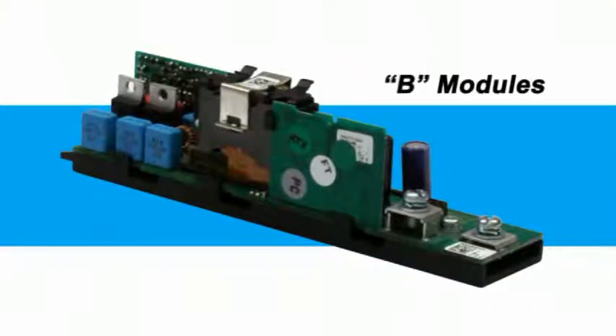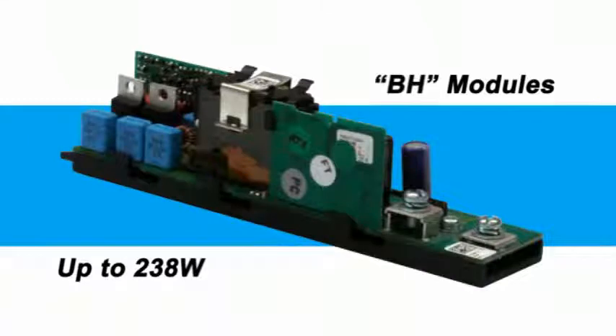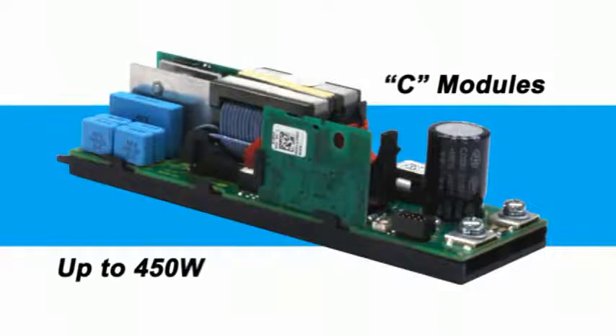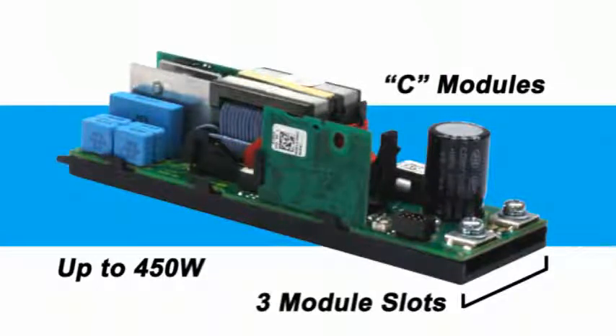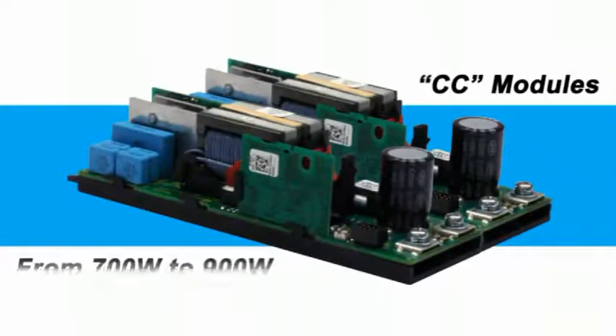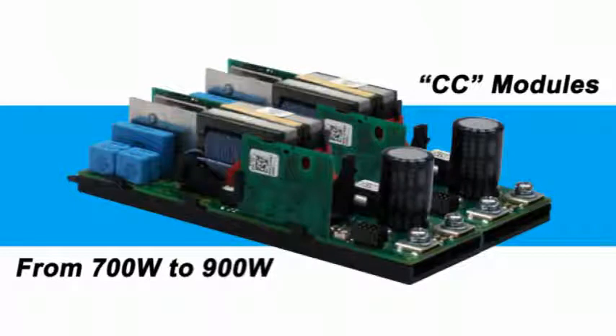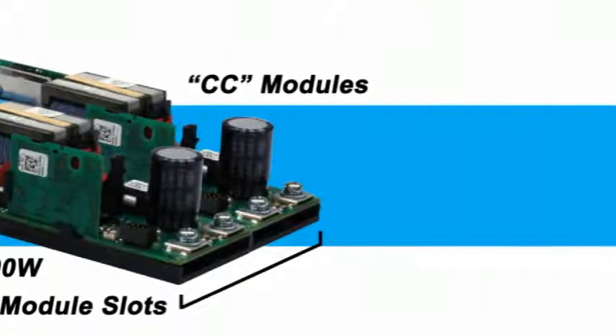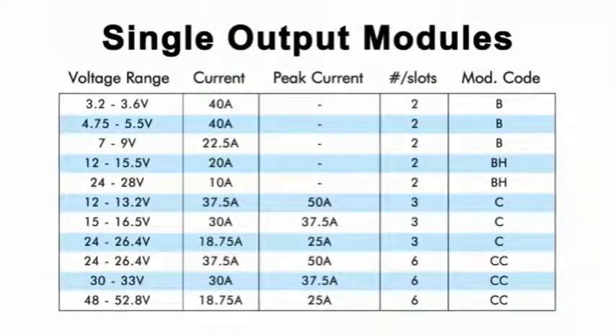These include the B modules up to 200 watts and BH modules up to 238 watts that take up 2 module slots. The C modules up to 450 watts are 3 slots wide and include a microprocessor to increase its power density, performance, and reliability. The CC modules from 700 watts up to 900 watts use 6 slots of space. For special voltages, each module has a wide adjustment range. Any combination of output modules can be used as long as they fit within the NV700 8-slot mainframe.